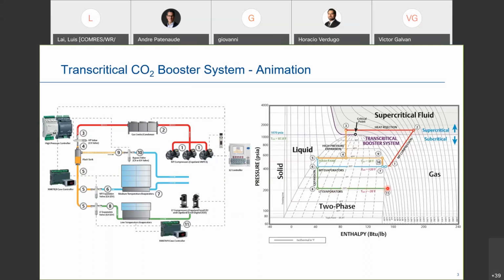Then it needs to pick up an additional 36 degrees of superheat, Fahrenheit, on low temp, but we'll talk about that later. But what happens after that, it goes to your low temp compressor. Low temp compressors now discharge into the suction line. On the left, compression ratio, increased compression, it gets to 12, discharging into the medium temp suction, and that medium temp suction automatically starts de-superheating that gas. It de-superheats it because it's got a mixture of medium temp suction, it's got a mixture of bypass mass flow, which has a little bit of liquid left in it, and that de-superheats the gas before it gets to our medium temp compressors. So that's kind of the stage, and it just keeps moving around and around in that same fashion.